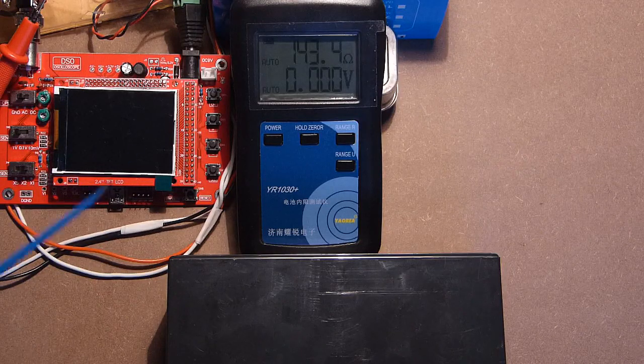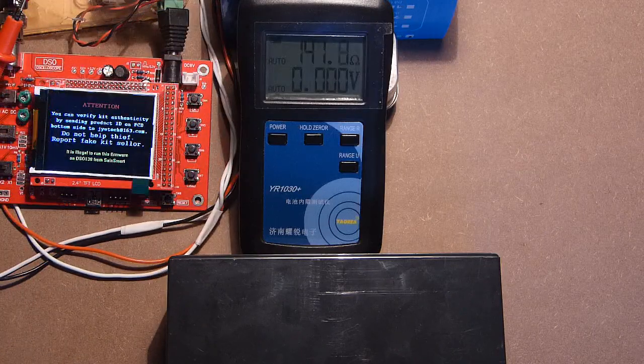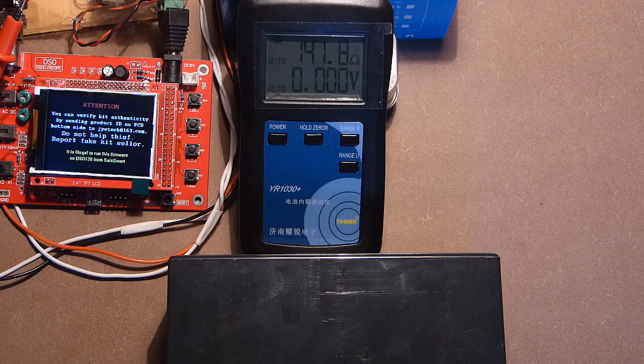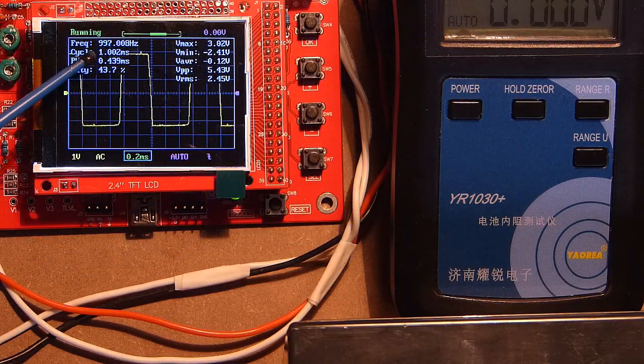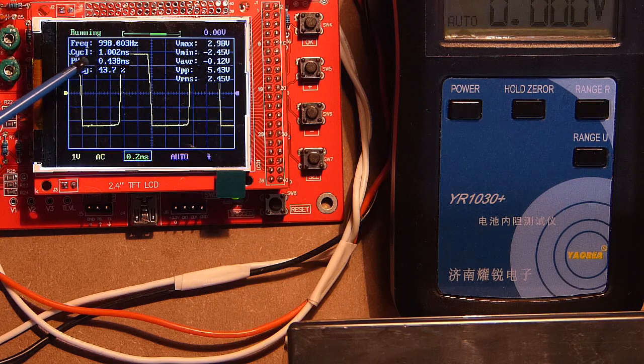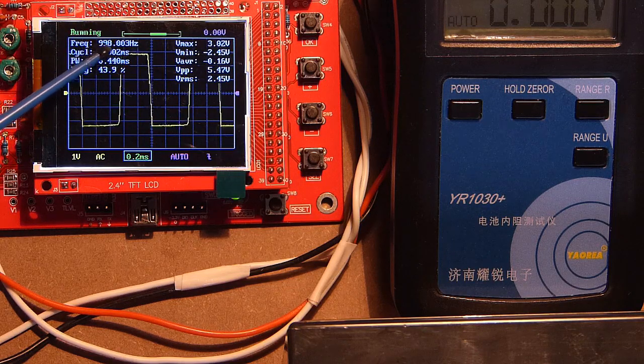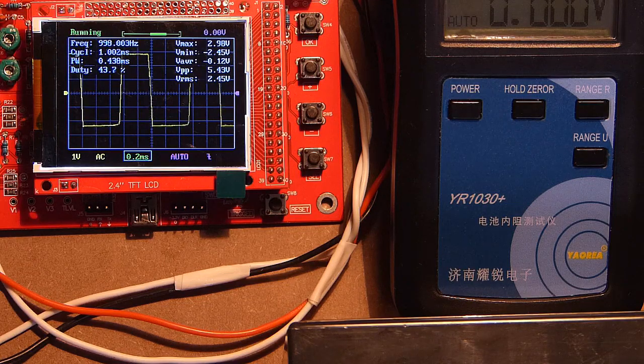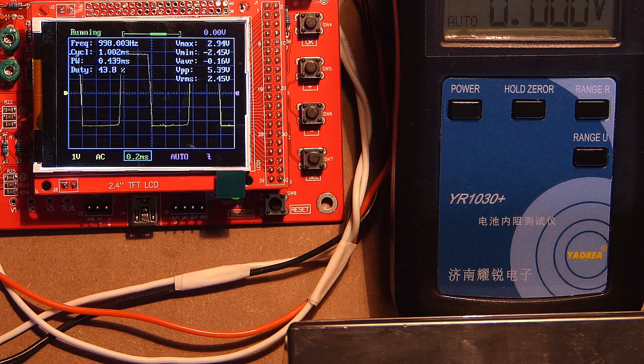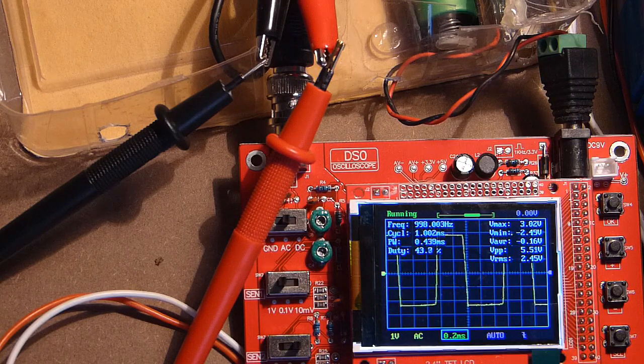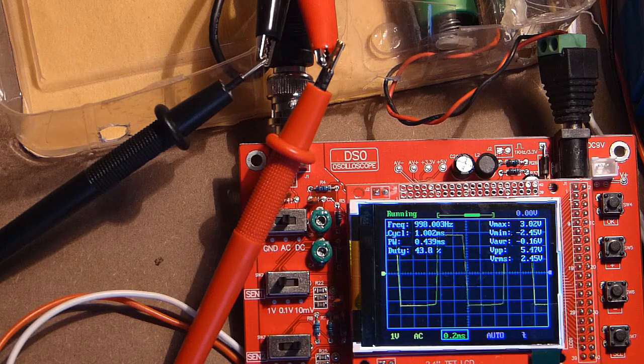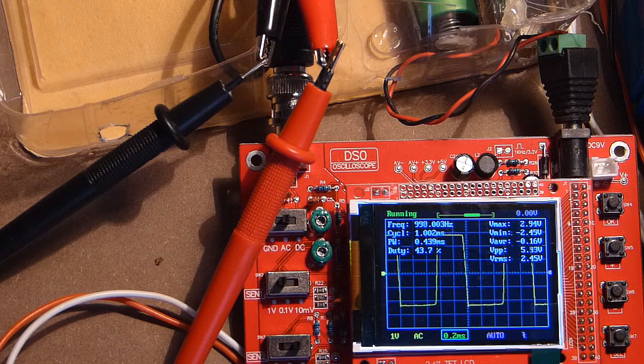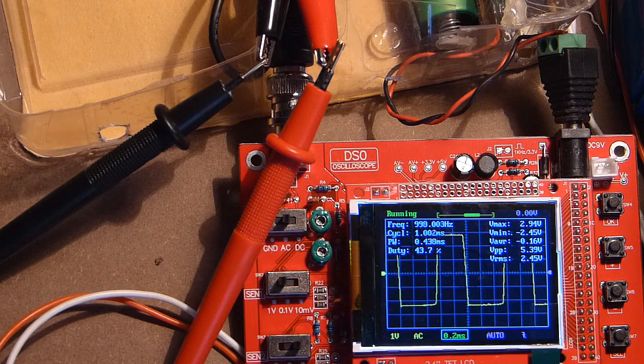And finally, let's check the frequency of this device and its waveform. 997, 998, sometimes 999. So we can say that the frequency is really 1 kHz and the waveform is square. Also, please pay attention to the fact that the oscilloscope probes are connected directly to the impedance meter probes. Otherwise, we will have distorted signal, like this.